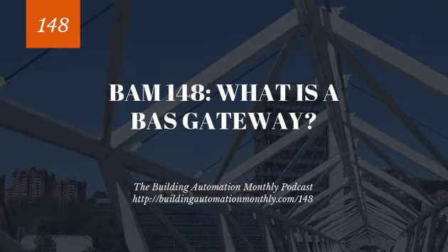Physical gateways are gateways that connect physical media together. So for example, if you needed to take wired to wireless, or RS-485 to 232, or you needed to go Ethernet to MSTP, because IP is not a physical protocol. That's a whole other can of worms. Just realize that if you try to equate IP with Ethernet, that is actually an error in understanding. IP is a logical protocol, meaning it does not physically exist. Oftentimes when folks are saying IP, they're thinking of Ethernet.